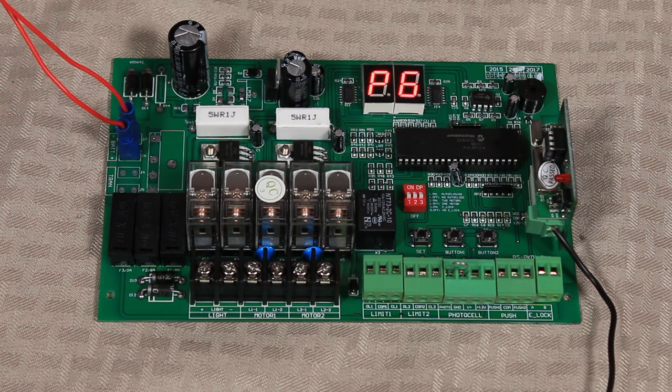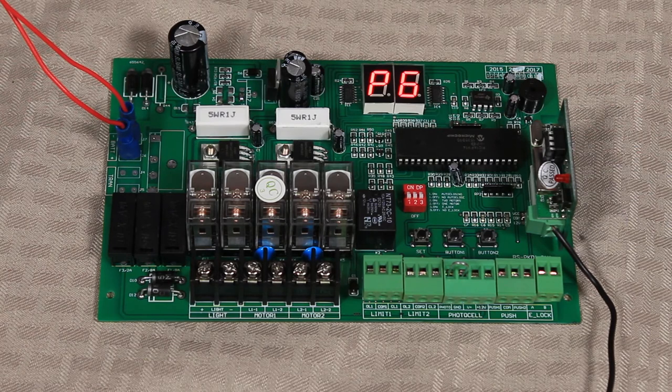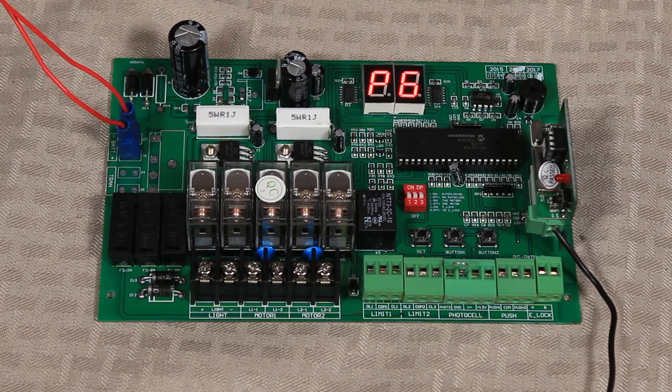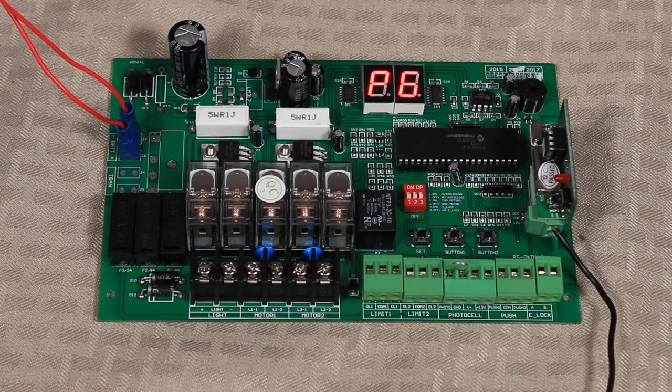The setting goes from zero all the way up to 99 seconds. What this means is once the gate reaches the fully open position and hits that open limit switch, it will stop and the timer will start, meaning AU will come up on the display.